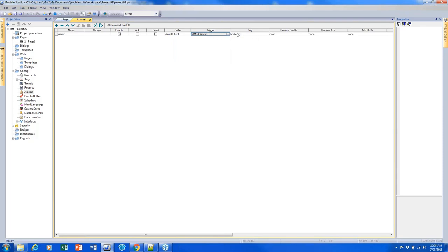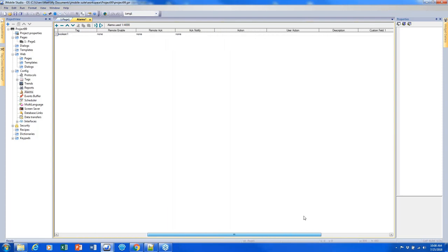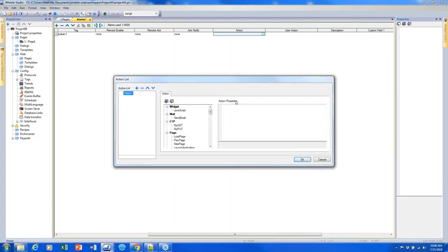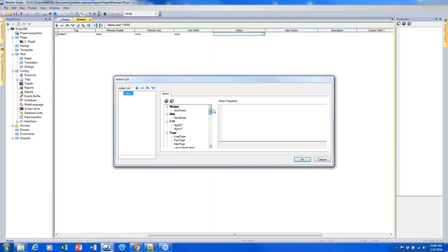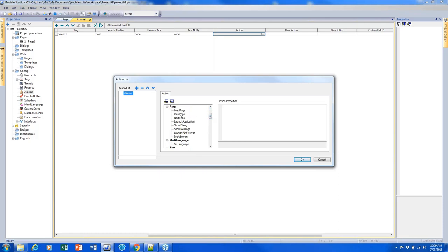It picked my boolean tag, which means there's only one bit we could choose from. So whenever my boolean tag one gets flipped to a one, the alarm would be triggered. I want to go through and completely explain the behavior of one alarm first. Whenever my trigger is thrown — the value of tag one is a one — some action will be executed. We add the action by clicking this square and selecting from our action list, similar to the action list you'd see with a button.